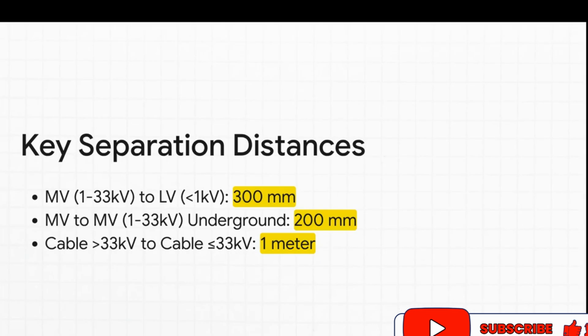It's a huge deal. And it doesn't stop there. The standard is packed with other separation rules to stop electrical interference. You need 300 millimeters between a medium voltage and a low voltage cable. And if you have a really high voltage cable, anything over 33 kV, you need to keep it a full meter away from any lower voltage cables. These rules are just fundamental for a stable system.